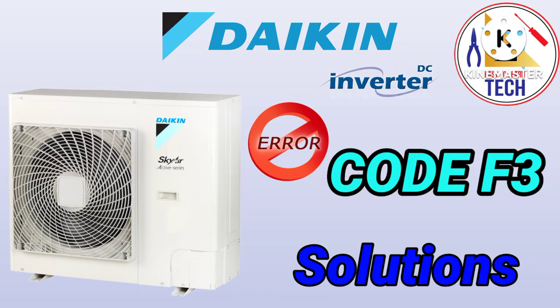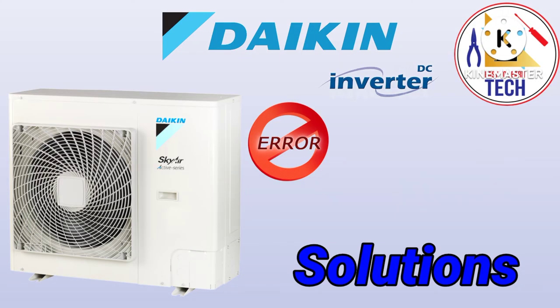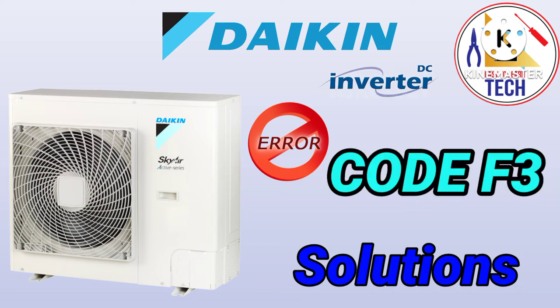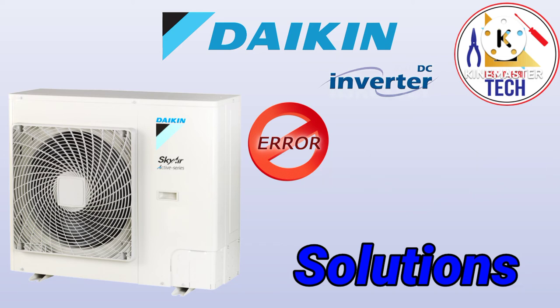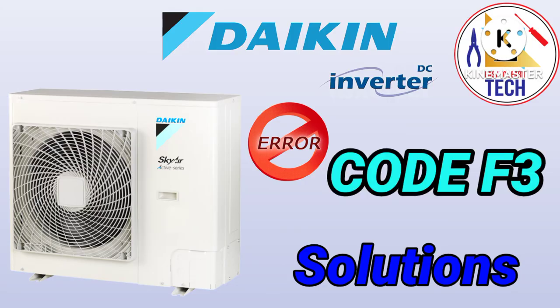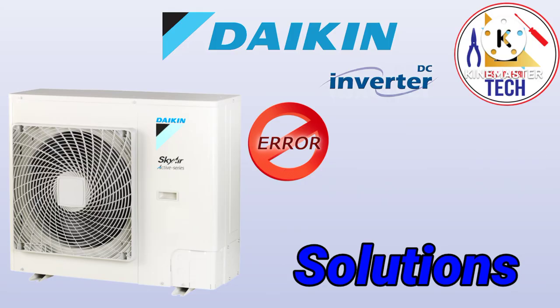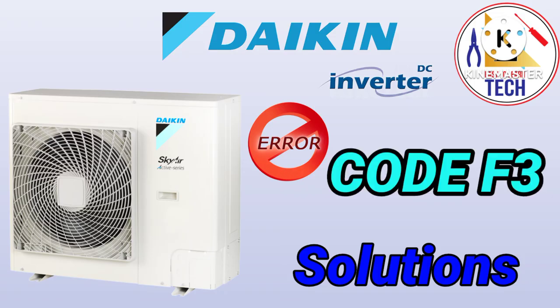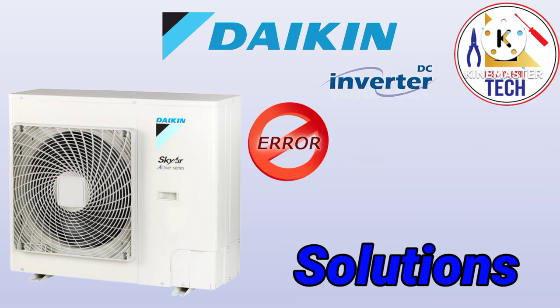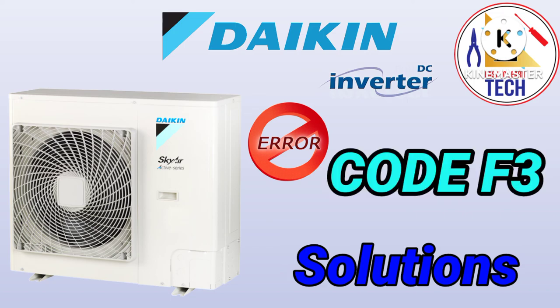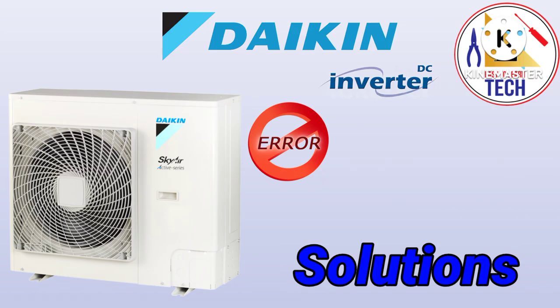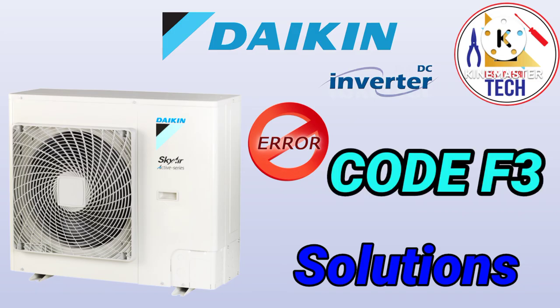And when you see these two things, that our condenser is clean and there is no clog in the refrigerant piping area, then you have to check the discharge temperature thermistor. If the resistance is not showing properly, it means our sensor is faulty. If the resistance is showing properly in our temperature sensor, it means our temperature sensor is good. Then you have to check the output supply of your outdoor PCB. If the output supply is not good, it means our outdoor PCB is faulty. You need to change the outdoor PCB and you will get the solution for the error F3.